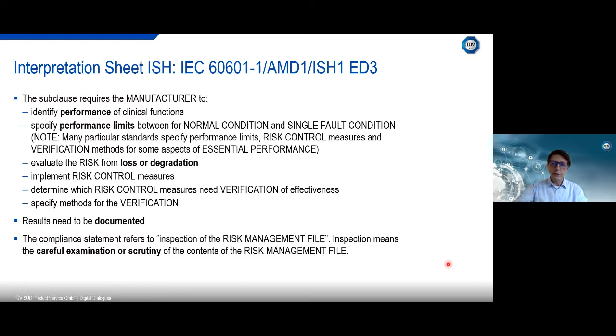Now also let's have a very short look at the clarification on the single fault condition. It applies to both basic safety and essential performance. Single fault condition means we have a defective or a single abnormal condition present. When the initial failure remains undetected, we need to have a second failure, which then can be detected. The risk analysis is used to determine which single fault conditions are to be tested. So this should be an outcome of the risk management file, to have the details of what to test. And again, the documentation has to be done by the manufacturer, intended to serve as objective evidence. So these parts in this interpretation sheet give a little bit more information for you as a manufacturer, as well as for notified bodies and test labs, on how to handle this part.